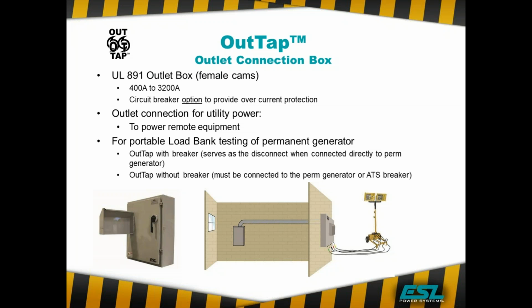So as I mentioned earlier, we've had a lot of occasions in the past where we've provided temp taps or storm switches to back up the permanent generator. And now the client's coming back and saying, okay, I've had some issues. I need to start load banking my permanent generator. And I don't want to have to do it the old fashioned way and open up the generator and get into a circuit breaker and connect and disconnect a whole bunch of cables and all of that.